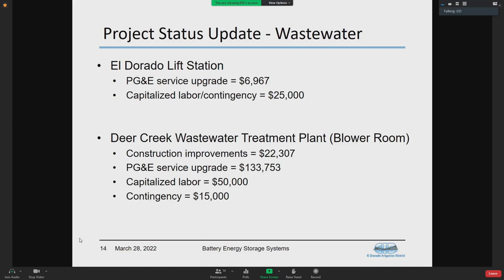What's not fully shown on the slide is that the switchgear at Deer Creek has been an ongoing safety issue for several years. It's older equipment and doesn't have proper arc flash facilities. We looked at a project about 3 years ago to replace that switchgear, and the initial estimate came back at 2.1 million. So by working with Tesla to do this project and paying $133,000 for our service upgrade, we avoid a long-term safety and fiscal liability for replacing that switchgear.